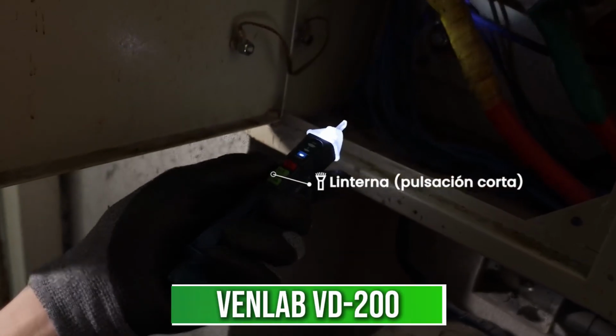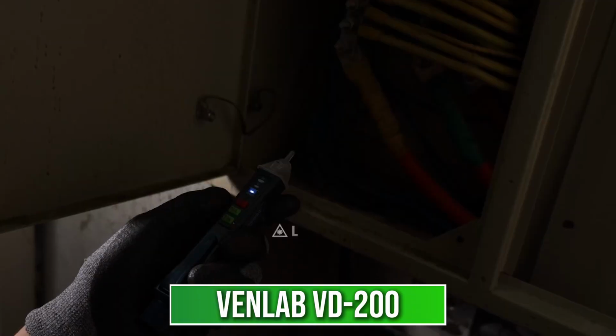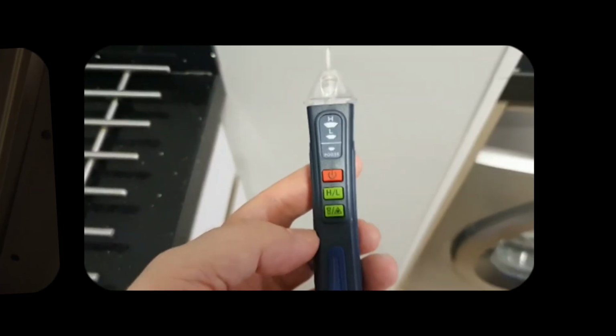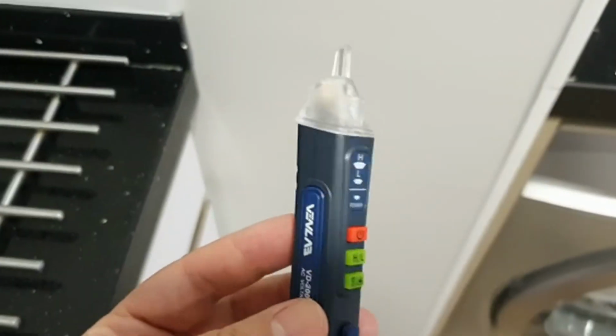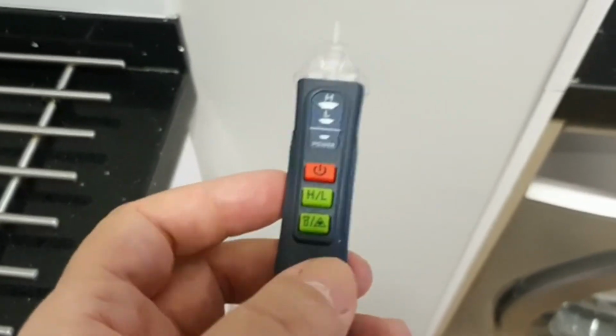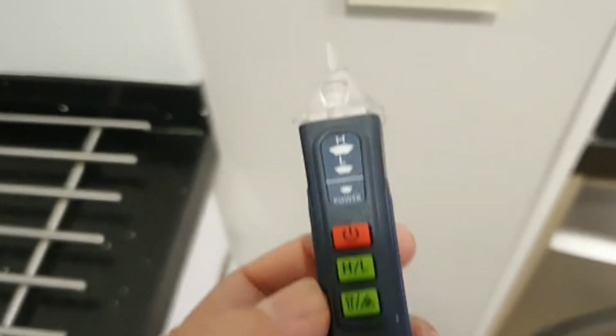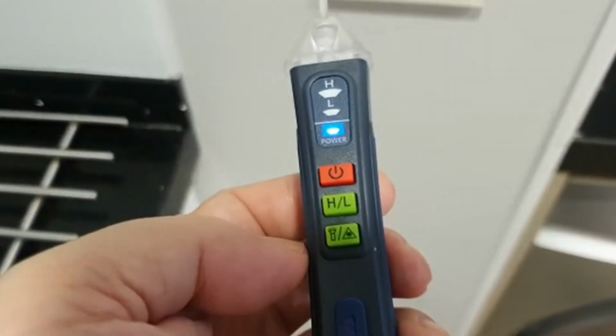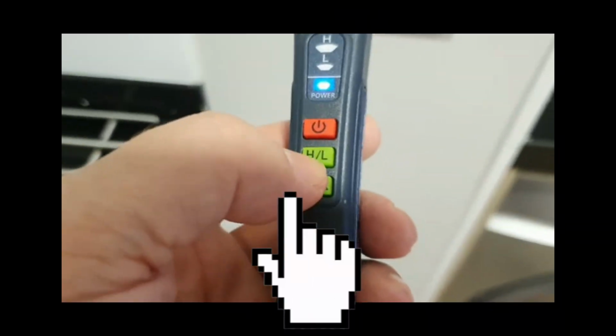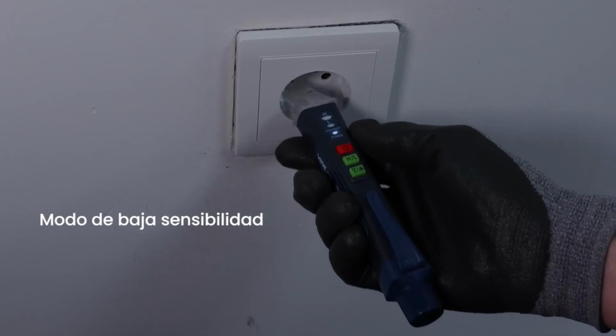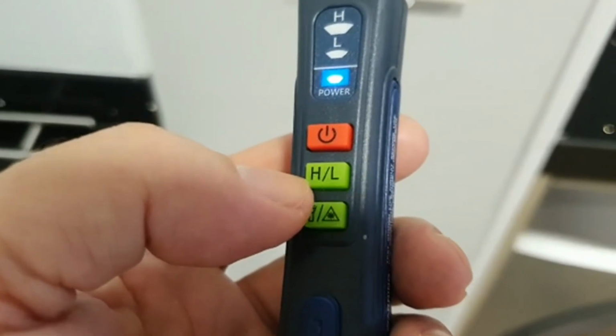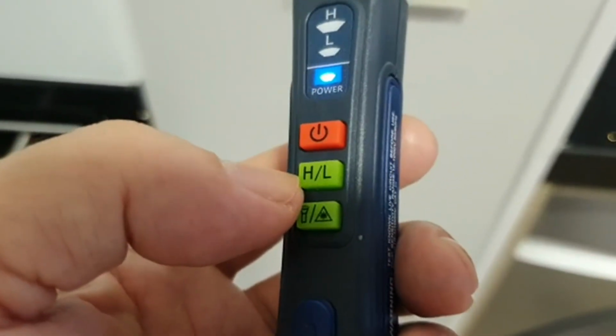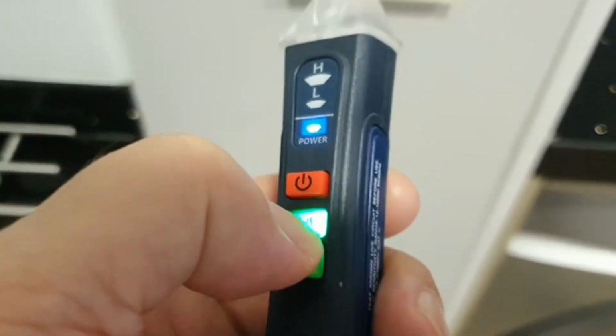We start with the Venlab VD200, which behaves less like a pen and more like a pocket diagnostic station. It gives you 2 switchable ranges, a standard 48 to 1000 volts for normal installation work, and a high sensitivity mode from 12 volts for thermostats, telecoms, and low voltage lighting. On top, you get a backlit LCD, a laser pointer, a torch, and a housing-rated CAT3 at 1000 volts and CAT4 at 600. One design touch I really rate: it always boots into low sensitivity, so it doesn't shriek the moment you pull it out of your pocket.